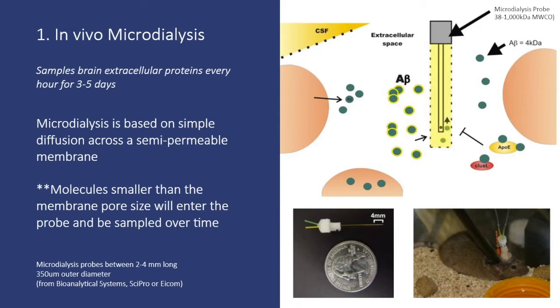So in vivo microdialysis, the way this works is you implant a probe with a semi-permeable membrane at the tip. Molecules that are small enough to cross that membrane can enter the probe. They run a solution to the probe at a constant flow rate, usually for us a microliter per minute. And you can sample what diffused into your probe over time. So in 60 minutes, we get 60 microliters of fluid, and then we run that on an ELISA or a Western blot, or people have done mass spec, to be able to see what kind of proteins or what's happening in the brain over time.